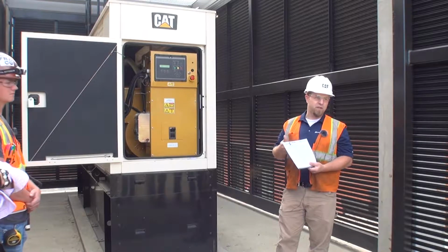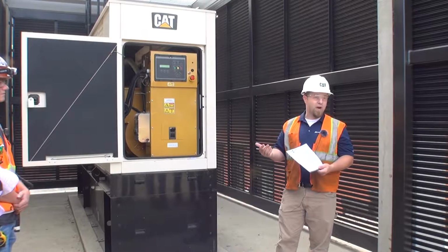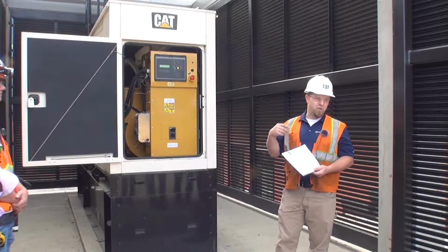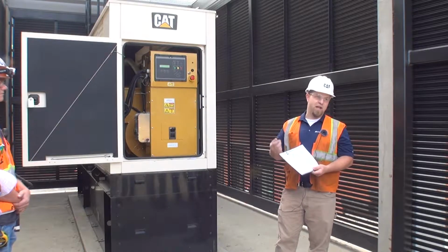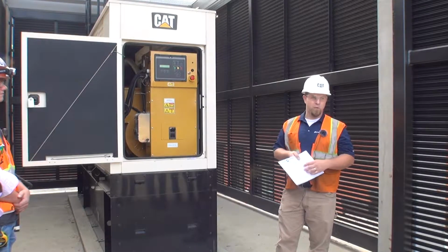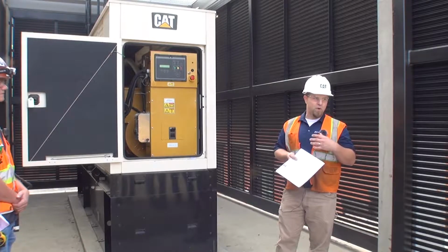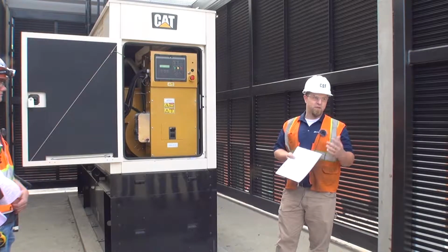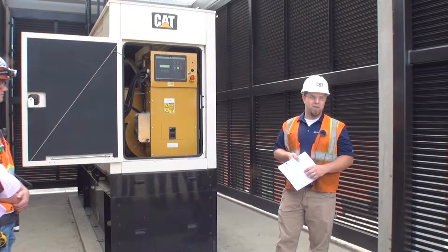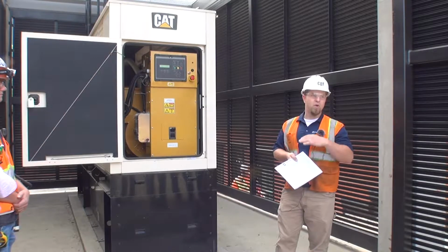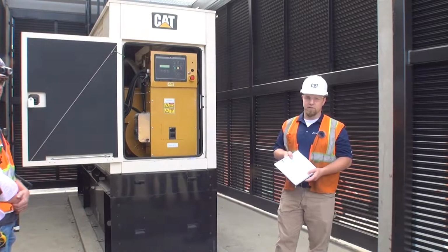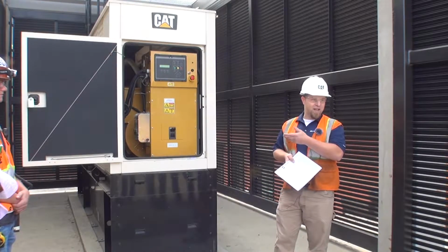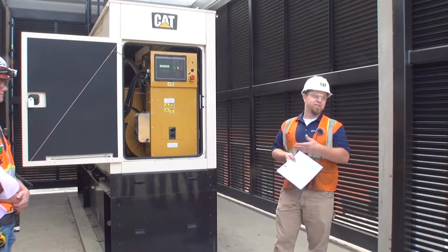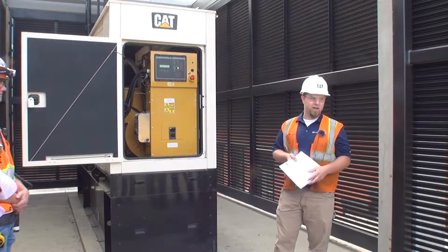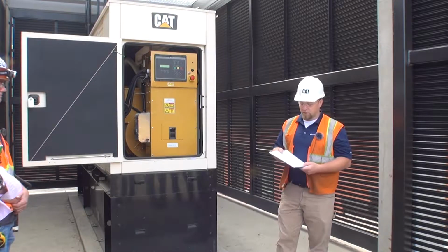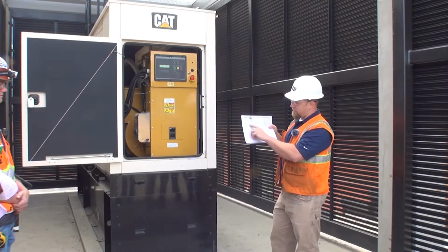My personal suggestion is that if you have a power outage that's more than 12 hours, get on the phone, get your name in the queue, get on the list, because everybody else in town is going to be calling for fuel too. Even though Carson and everyone else does a really good job, when you have that many people calling in, it's whoever was on the list first. So if you have more than about a 12-hour run time, I'd be getting on the phone, or at least have somebody here check in where your level's at. Just my recommendations. I see in the snowstorms, usually somebody's sitting at like 60-70%, thought they were good, start burning for 2 days, and then they're panicking to try and get fuel. It never works out well. So that's where the fuel is. We say above 75, below 90.